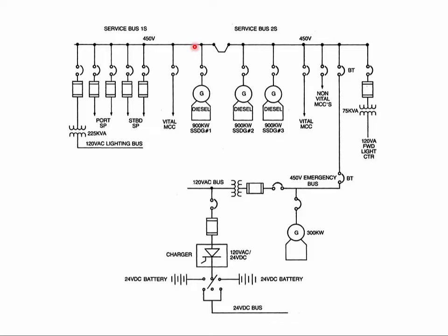And the other thing you have to realize is that you cannot synchronize the emergency diesel generator with the main generators. The governor system and the automation is typically not set up on the vast majority of American vessels to be synchronized. So the worry is that you would start up a diesel generator while on feedback and put it on the line without synchronizing it. And again, the automation is typically not set up to synchronize.